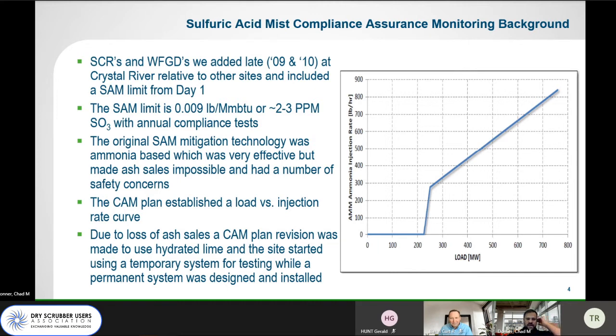The CAM plan was based off of, or established, a load versus injection rate. So pretty simple. There wasn't any real consideration to changes in fuel SO2. It was purely an injection rate of SO3 mitigation chemical to load on the unit. And then shortly after operation, due to loss of ash sales, a CAM plan revision was initiated to include hydrated lime injection. The site quickly transitioned to a temporary injection system while a permanent system was being designed and installed.